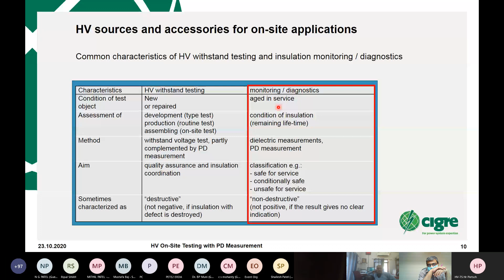I will concentrate on AC voltage tests. And then on site, if it's aged, for example after 5 years, or you test just to see if it has aged, if something's going wrong, then you'd like to see what is going on on site, like gas and oil analysis, or I'm looking for the tan delta, dielectric measurements, power loss measurements, and the PD. And then the tricky part comes: what is really going on, what can I do? And mostly it should be non-destructive, because all the systems should still be in operation if the values are okay.